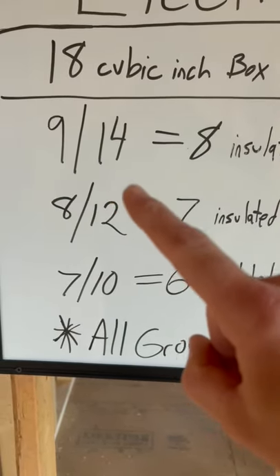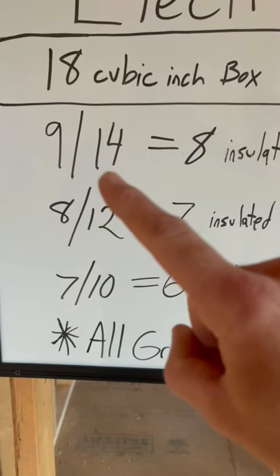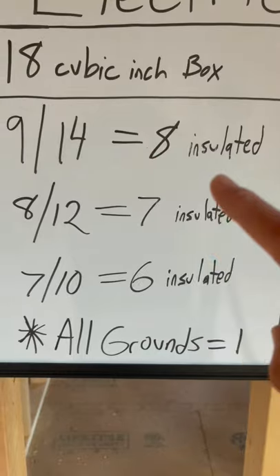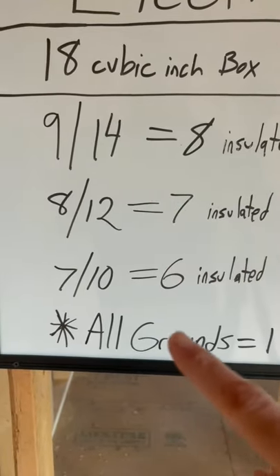So the 9/14 means you can have nine wires that are 14 gauge, and you can take one out for the ground, so you can have eight insulated conductors because all the grounds equal just one.